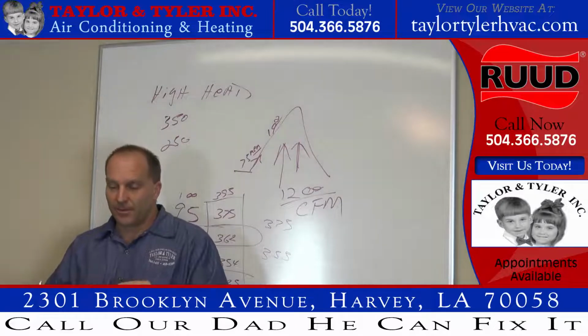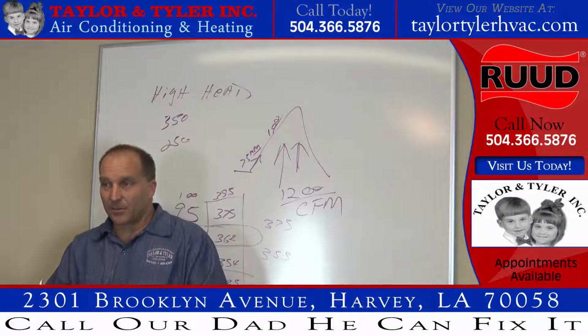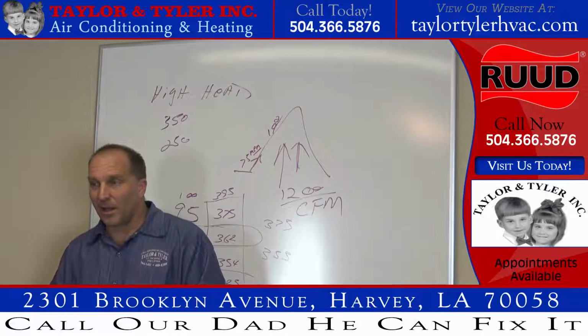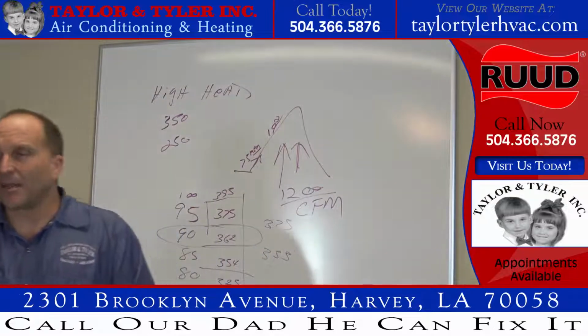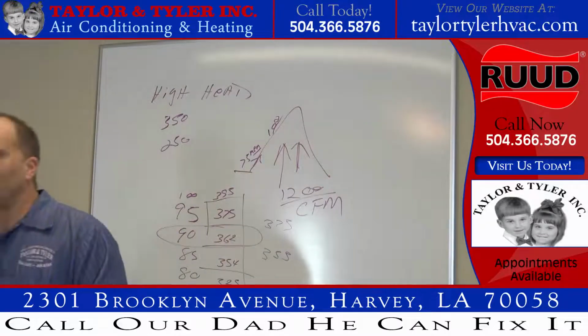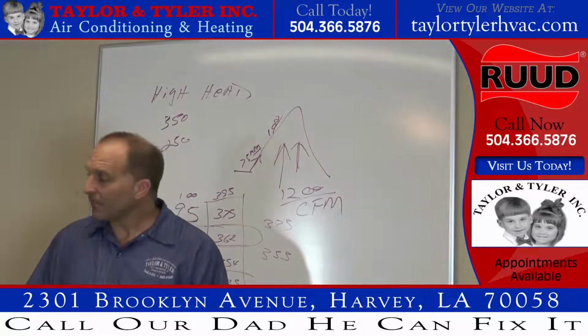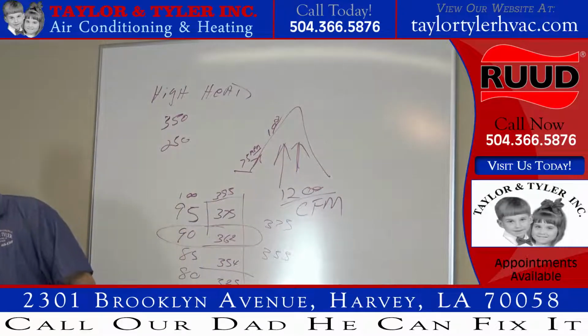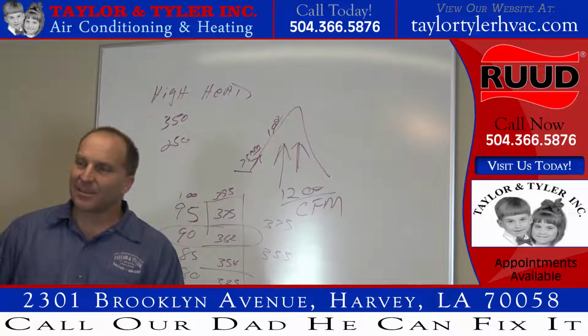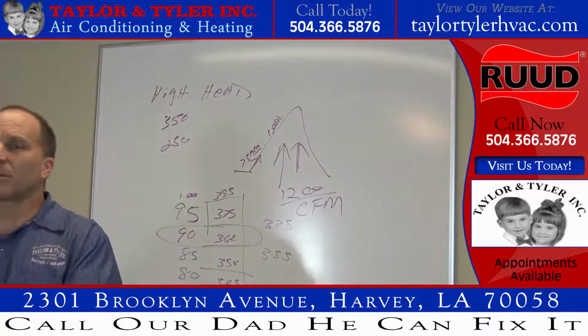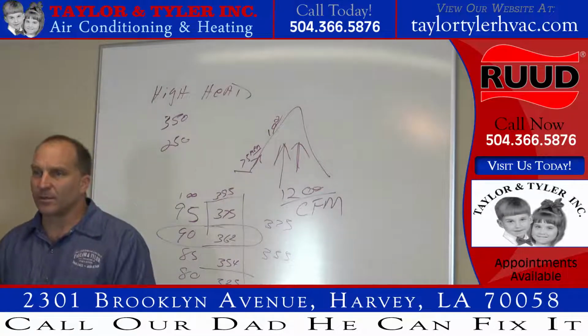And I put a T in there, a Schrader valve pin, and then I went ahead and I put my gauge inside there, and I tapped my gauge inside there, okay? So now I'm reading the high side of that system inside the condenser coming right out of the compressor, okay?